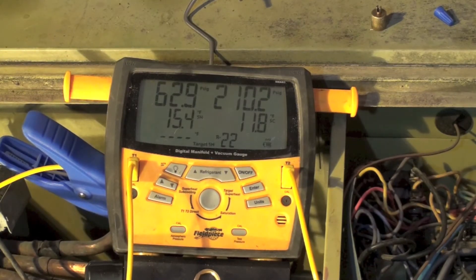Here we're going to compare the higher outdoor ambient. Let's look at the pressures. We're at 62.9 suction, 210.2 head, superheat 15.4, and subcool 11.8.